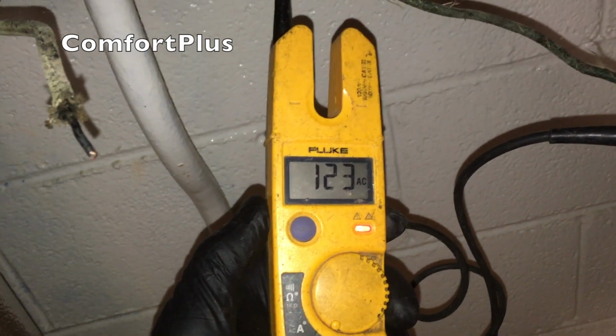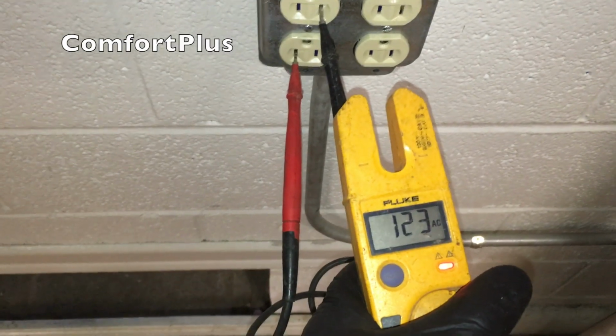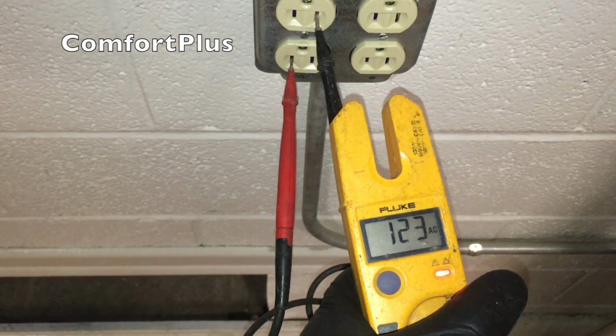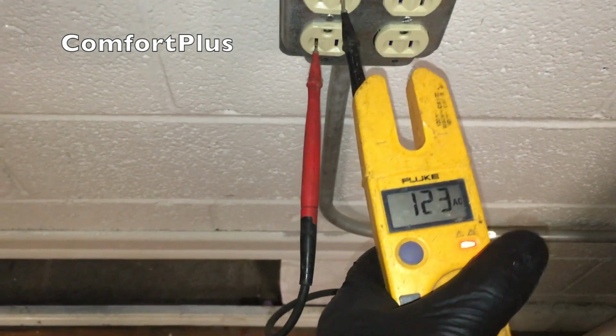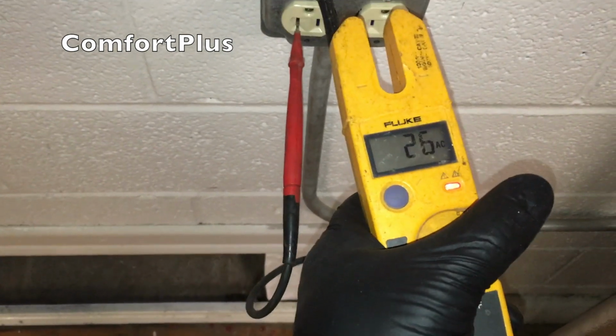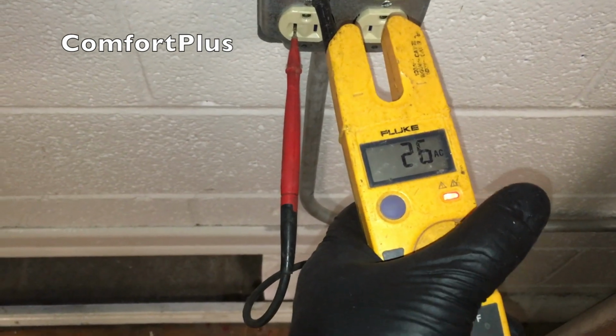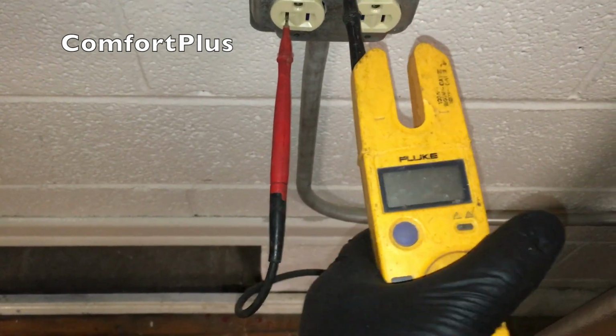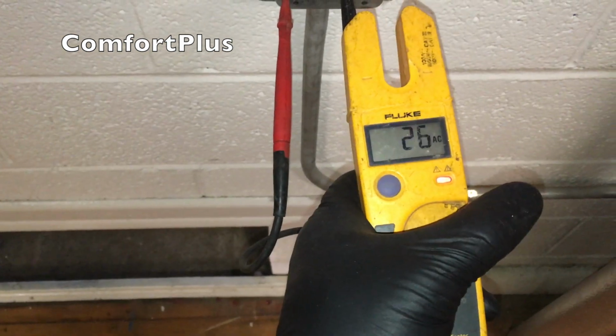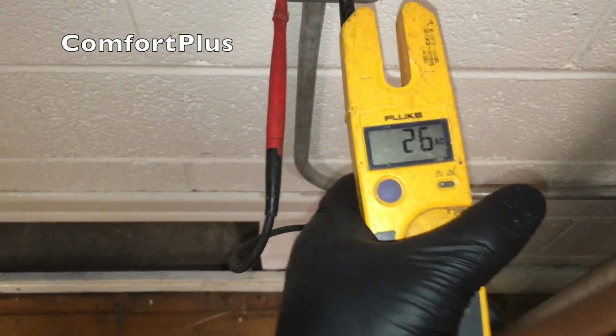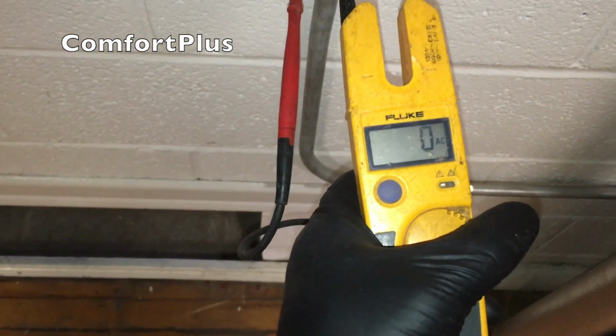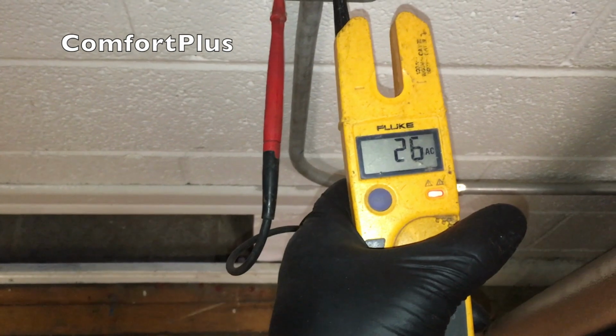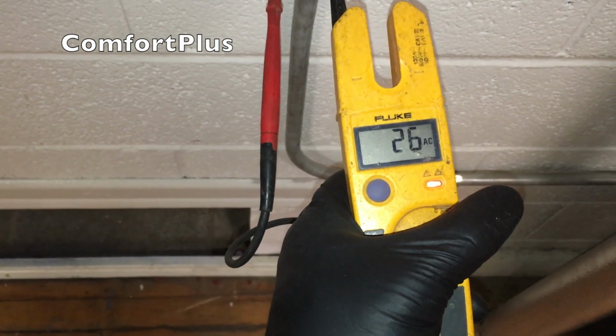Let me show you the other circuit. As you can see, we have 123 to neutral. We have 26 to ground. My meter's getting cold and freaking out over here—26 volts to ground. So more than likely, this circuit would not operate a furnace with a flame sensor.